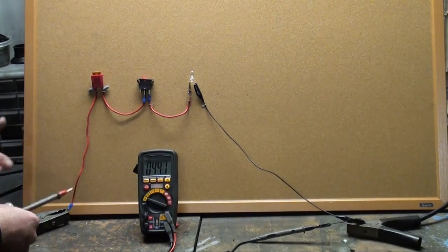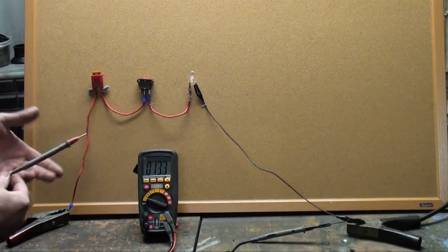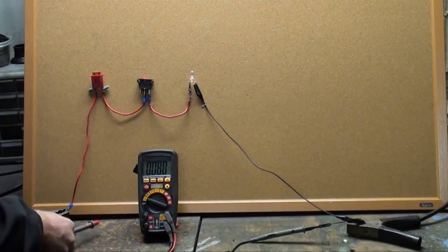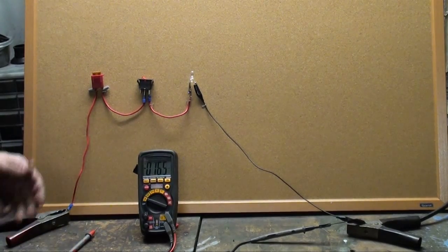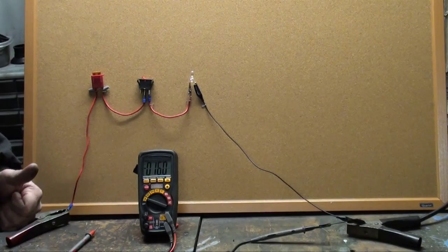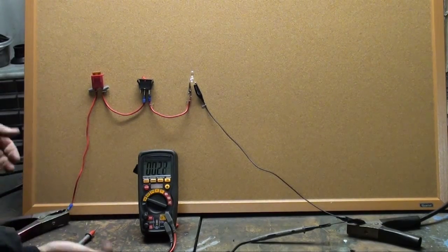It's because we have no voltage on that side of the switch. So how can we check that another way? We can do a continuity check. Now, in order to do a continuity check, you're going to have to open your circuit and disconnect your power.